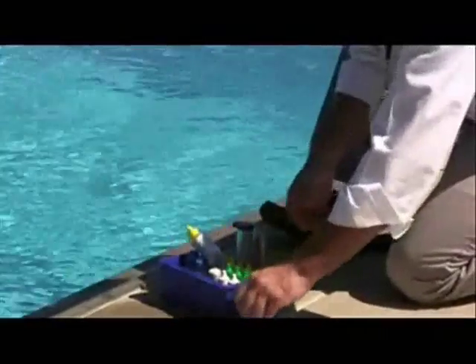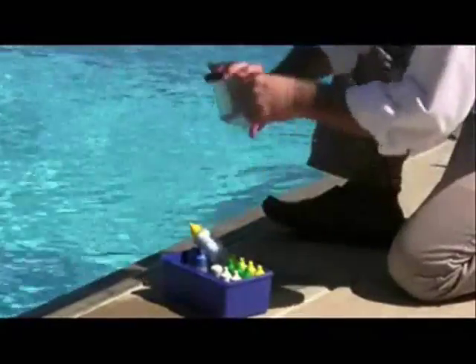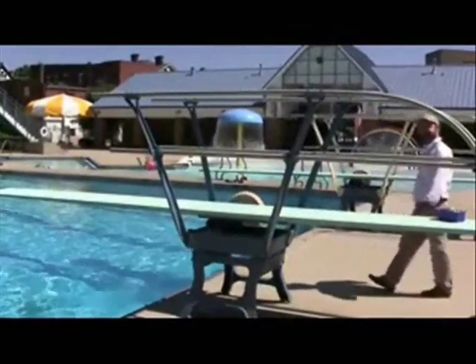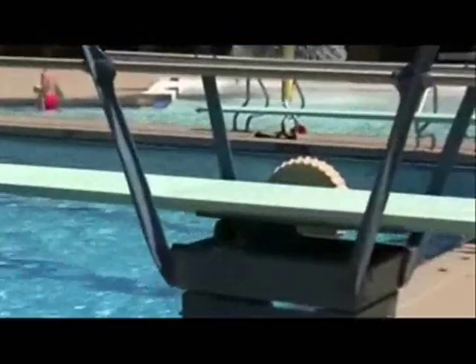But it's not just the chemical balance in a pool that matters. Tucker also checks to be sure the fulcrum in the diving boards are locked in the forward-most position. He checks to be sure there are at least two drains that are at least three feet apart. The drain covers should be Virginia Graeme Baker compliant, main drains must be in the deepest area of the pool, be covered by grates, and must be visible.